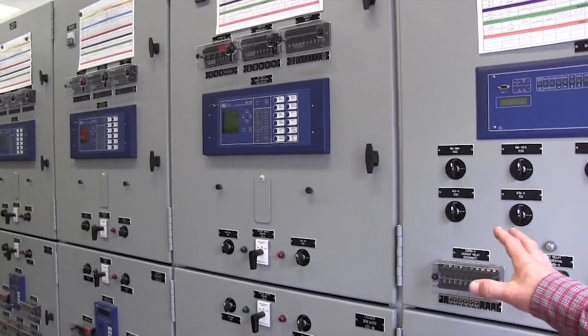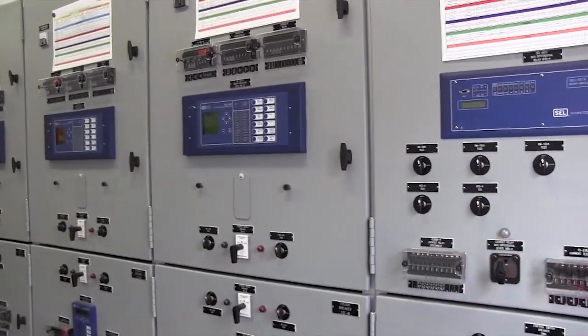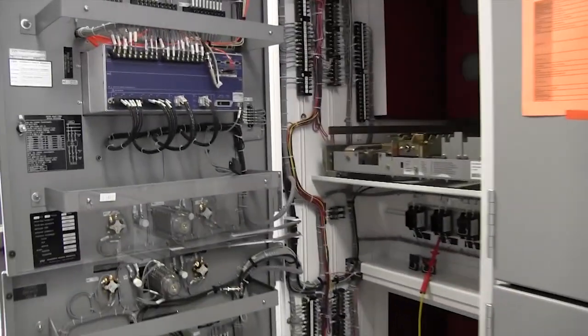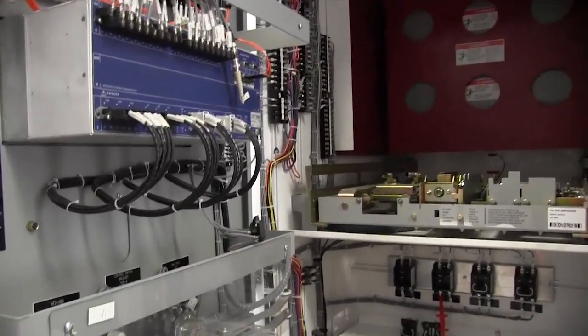This is the large version of what you have in your house, where a breaker is opened and closed. These gentlemen are doing all the acceptance testing for the substation — making sure that every one of those wires works and starts and ends where it's supposed to.